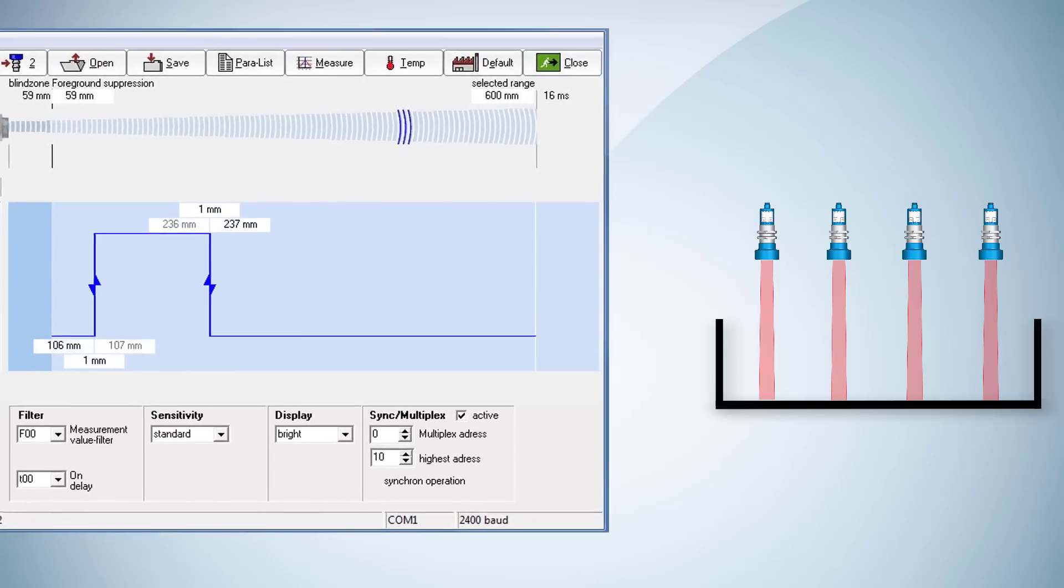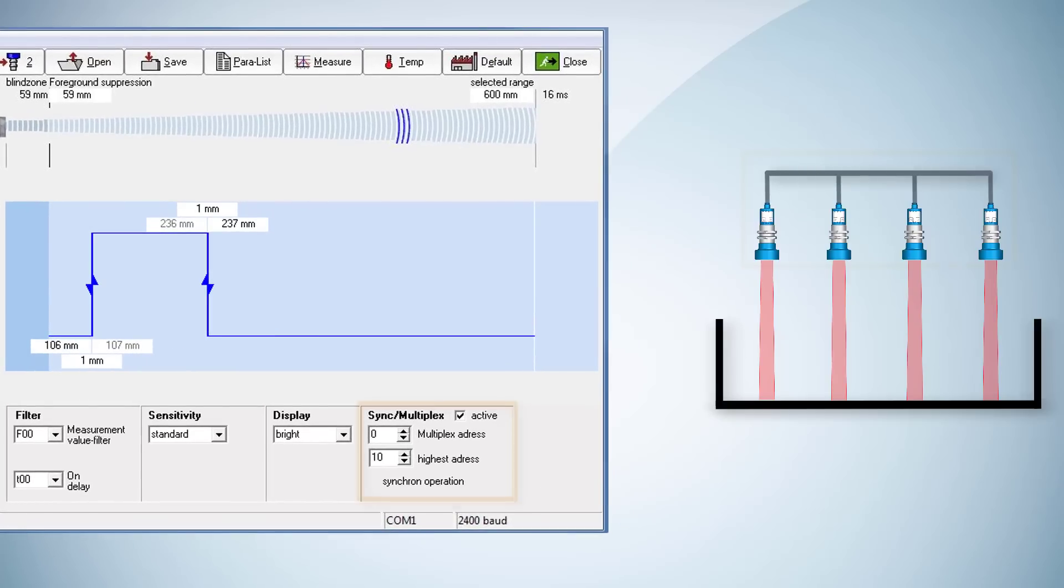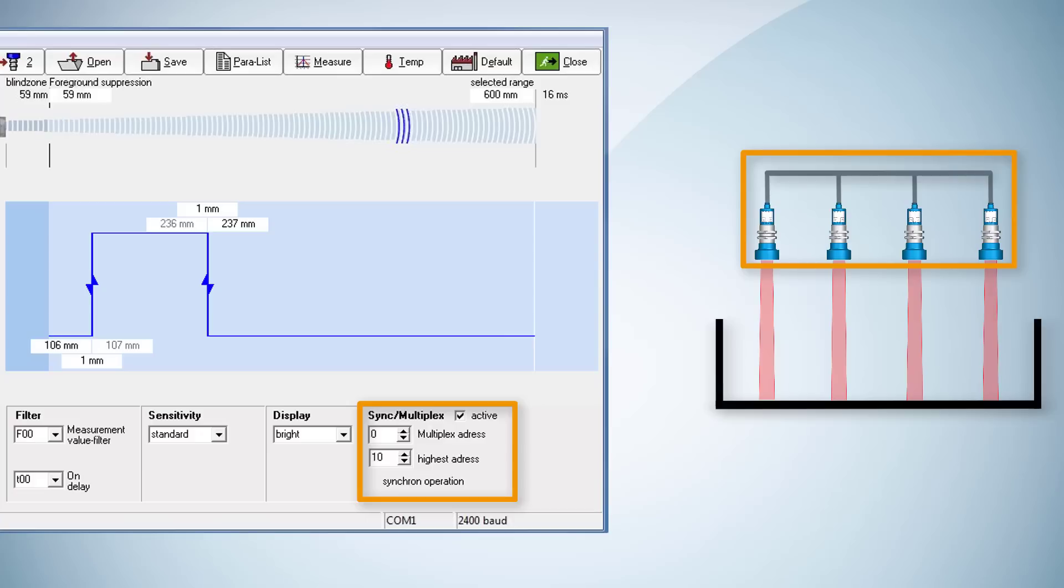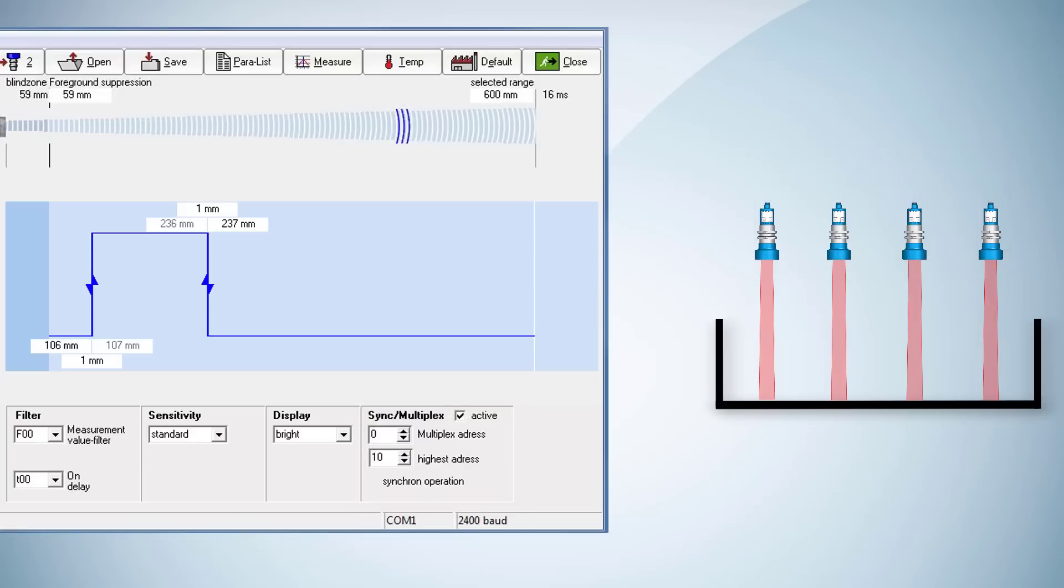All sensors work in synchronization mode which means that they send and receive the ultrasonic impulses simultaneously to avoid mutual interference. The synchronization mode is automatically set when the sensors are connected via pin 5.